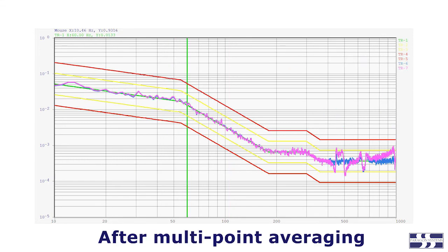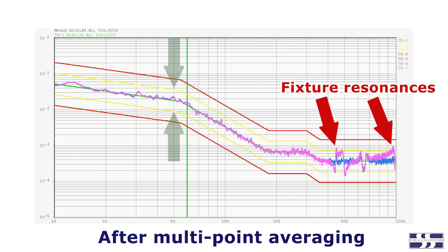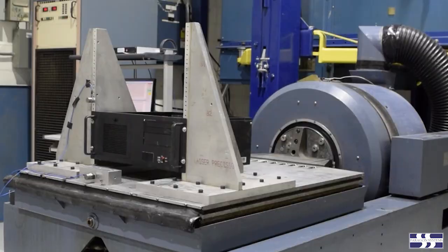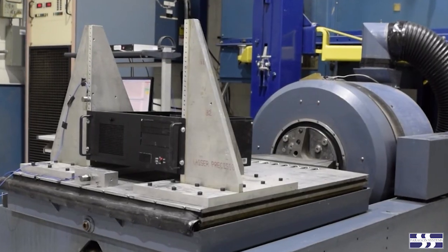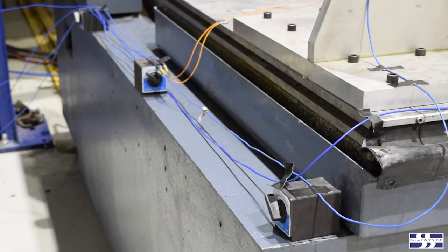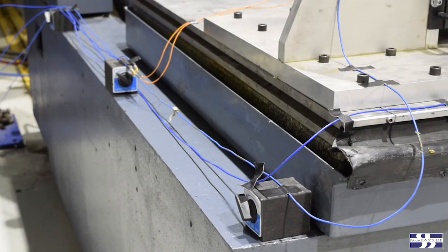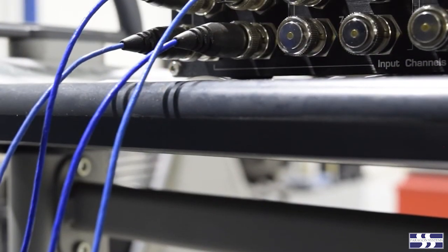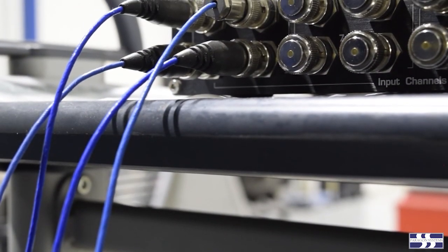Averaging does not correct fixture resonances. Instead, it permits the test engineer to use the full width of the test tolerance to bring the measured profiles into better control. Consequently, this technique should only be relied upon when reasonable efforts have already been made to design out resonances in a fixture.